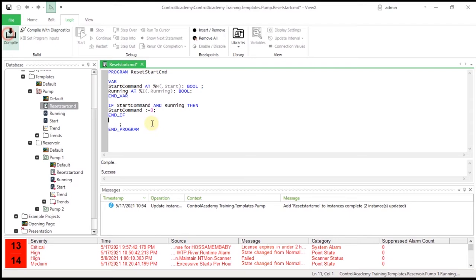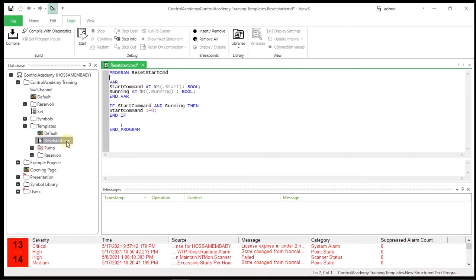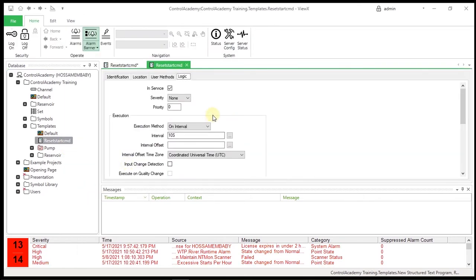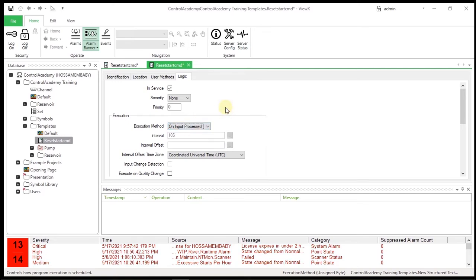We will run the structured text logic program that we created in the previous exercise. To display the logic form, right-click the Reset Start CMD logic program in the pump template, and then select Properties from the menu. Configure the execution method to use OnInputProcessed. OnInputProcessed tells the logic program to run each time the inputs are processed, which happens when they change. Note that only the running input triggers this program to run.